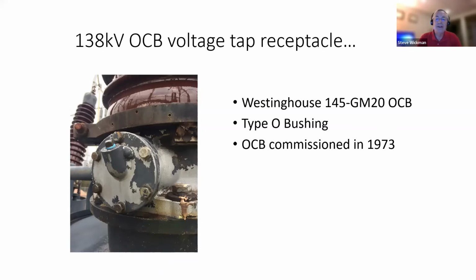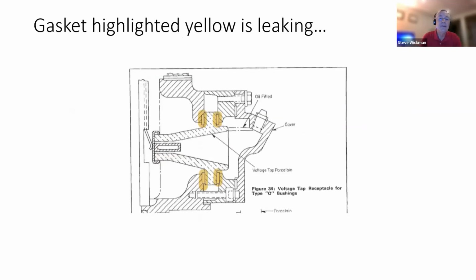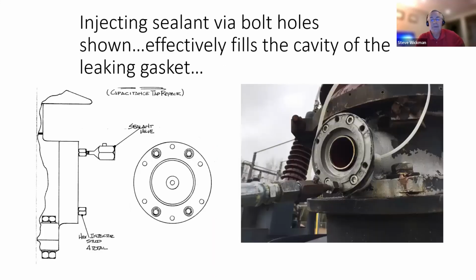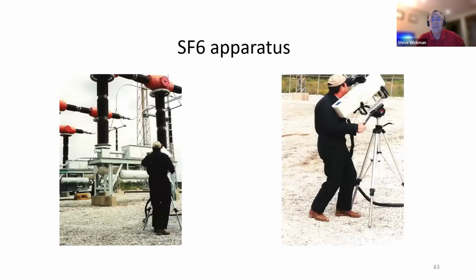But 1973 vintage, working with the customer, we determined that we could identify that this is where the leak was. There's little gaskets in there, and this is where the leak was. We found by taking the cover off that, we could inject the sealant compound into that cavity and then put that cover back on and effectively contain that leak for them.